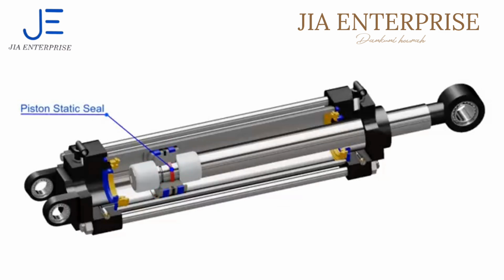A static seal ensures airtight sealing between the piston and rod. Piston guide rings are assembled to prevent metal-to-metal contact between the piston and cylinder. The piston seal provides airtight sealing between the cylinder and piston.